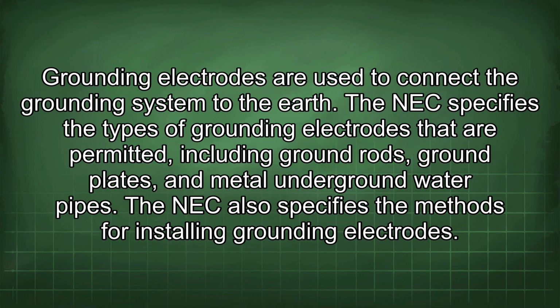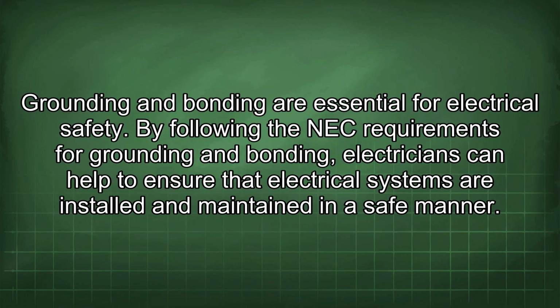Grounding electrodes are used to connect the grounding system to the earth. The NEC specifies the types of grounding electrodes that are permitted, including ground rods, ground plates, and metal underground water pipes. The NEC also specifies the methods for installing grounding electrodes. Grounding and bonding are essential for electrical safety. By following the NEC requirements for grounding and bonding, electricians can help to ensure that electrical systems are installed and maintained in a safe manner.